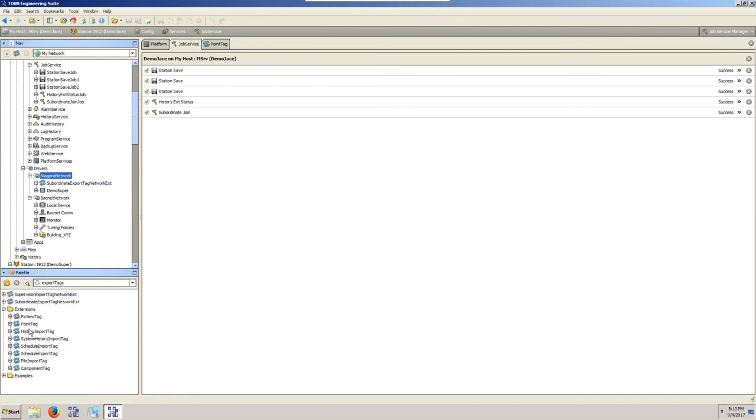with a PX view tag. Not a big fan of those. Sometimes it works really good, and the performance isn't too bad on the supervisor. Other times, I've had it just come to an absolute crawl. And this is something you don't want to find out after you've set up a ton of graphics and you messed around with getting this PX view tag to work right, to find out that it's so slow that you have to abandon that method.